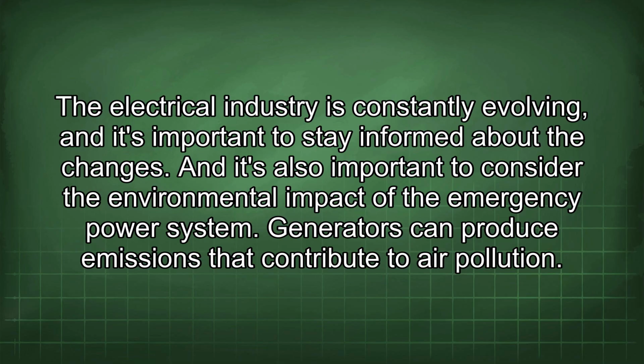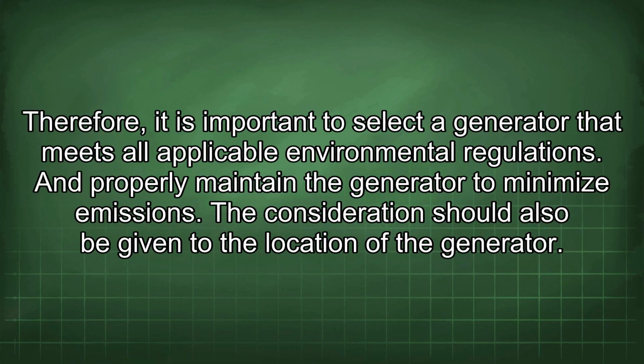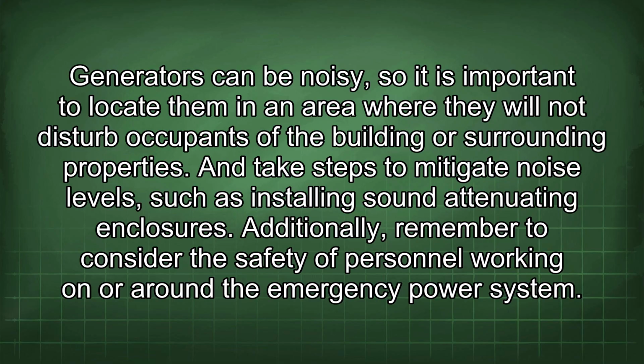And it's also important to consider the environmental impact of the emergency power system. Generators can produce emissions that contribute to air pollution. Therefore, it is important to select a generator that meets all applicable environmental regulations, and properly maintain the generator to minimize emissions. Consideration should also be given to the location of the generator. Generators can be noisy, so it is important to locate them in an area where they will not disturb occupants of the building or surrounding properties. And take steps to mitigate noise levels, such as installing sound attenuating enclosures.